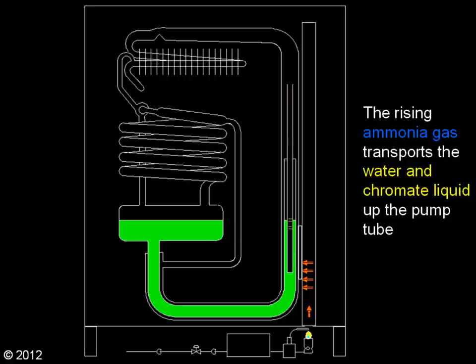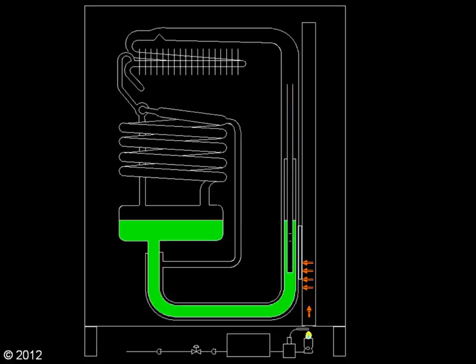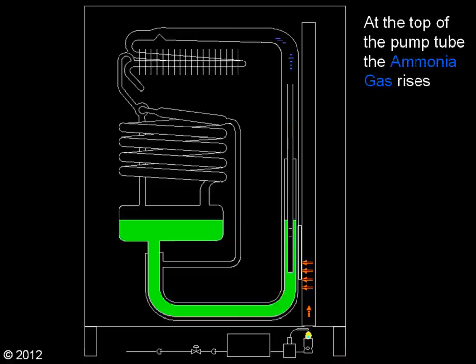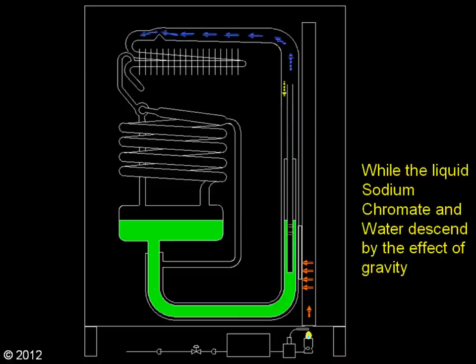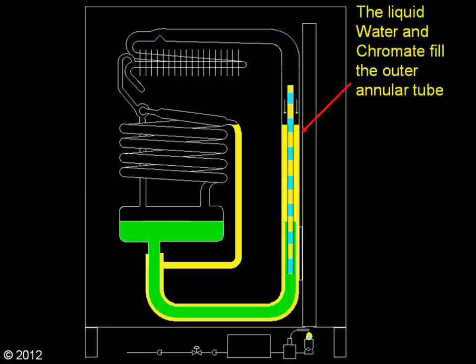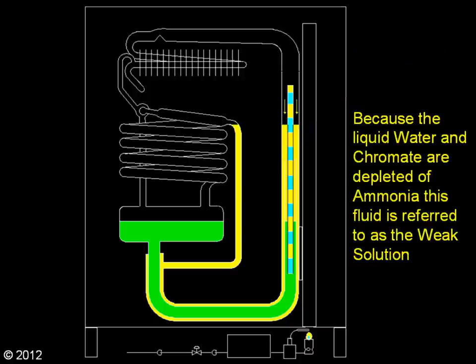The rising ammonia gas transports the water and chromate liquid up the pump tube. At the top of the pump tube, the ammonia gas rises, while the liquid sodium chromate and water descend by the effect of gravity. The liquid water and chromate fill the outer annular tube. Because the liquid water and chromate are depleted of ammonia, this fluid is referred to as the weak solution.